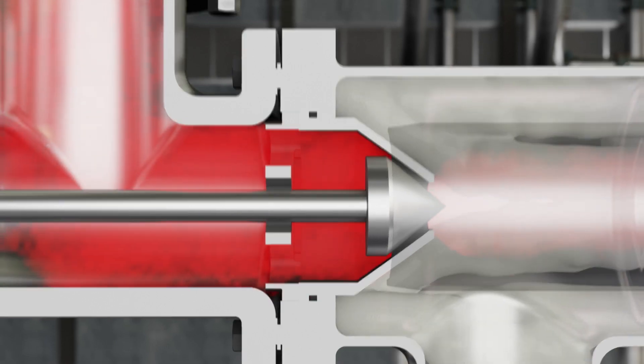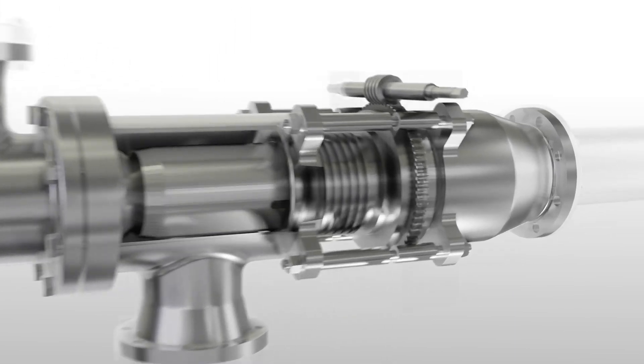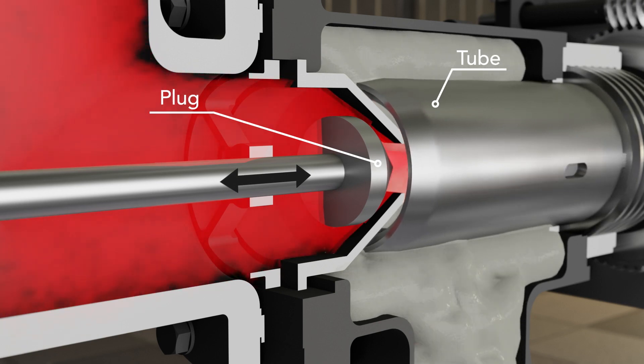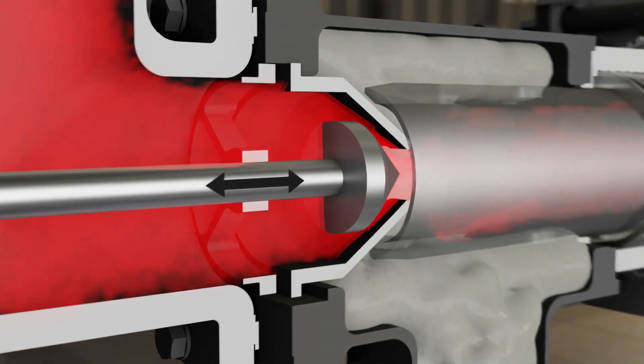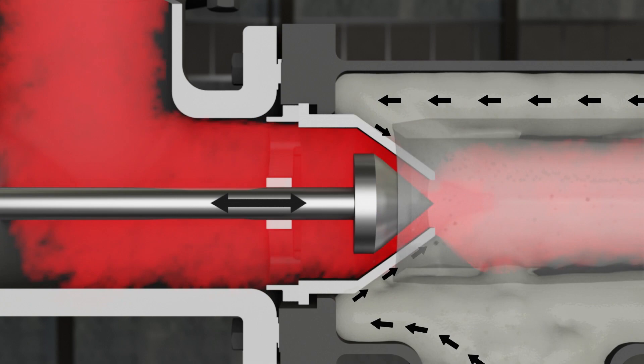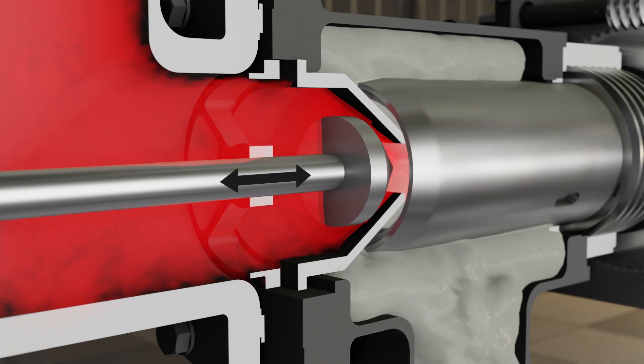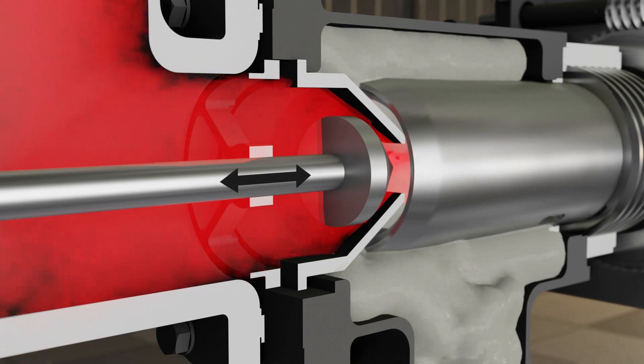The ProSonics OptiShear JetCooker's innovative design has performance-driven improvements over old-style jet cookers. Our cooker has a true mechanical drive mechanism which adjusts the slurry gap by rotating the steam condensing tube. Our gear reduction mechanism allows for precise forward and reverse movement of the steam condensing tube to maintain the optimum slurry gap. The adjustable slurry gap allows the operator to maintain a turbulent starch and steam mixing zone across a range of slurry flows, maximizing steam-to-slurry contact and ensuring complete and uniform heating of the starch slurry as conditions change in the process.